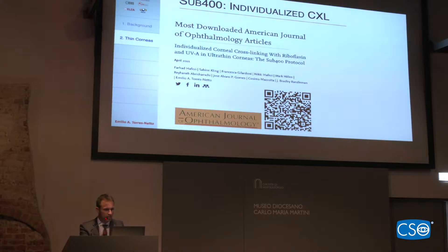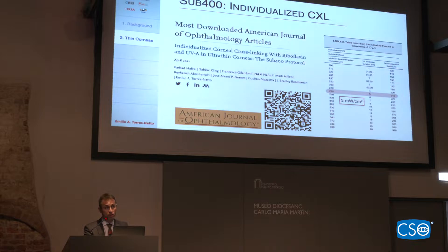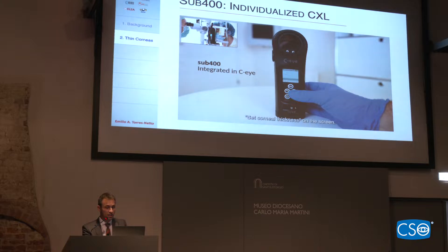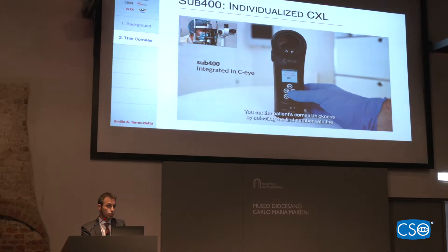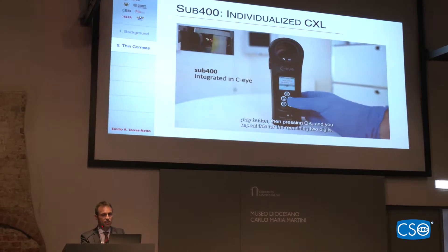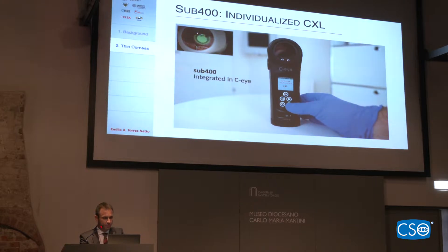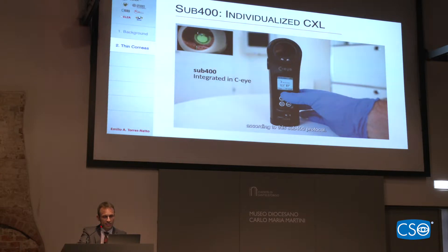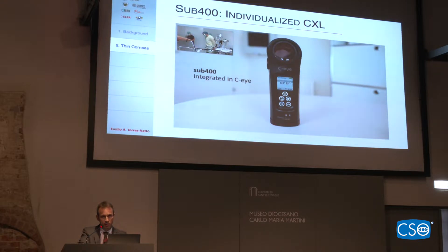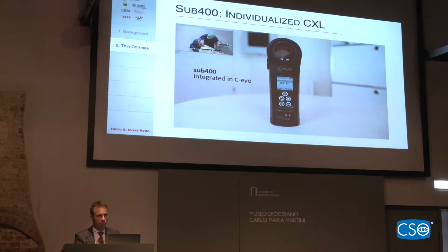The first point is about thin corneas. We published a paper in 2021 in the American Journal, and from then on we are able to treat corneas below 400 microns — that is no longer a contraindication. After one year we saw a flattening of about two diopters, comparable to the Dresden protocol. The C-eye device lets you input the thinnest pachymetry and it calibrates and adjusts the energy for each individual cornea.